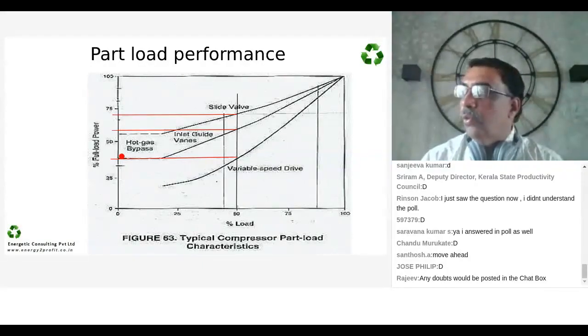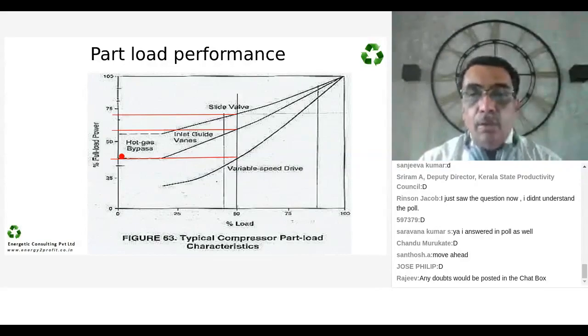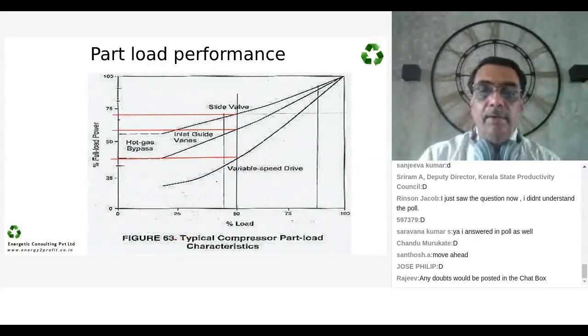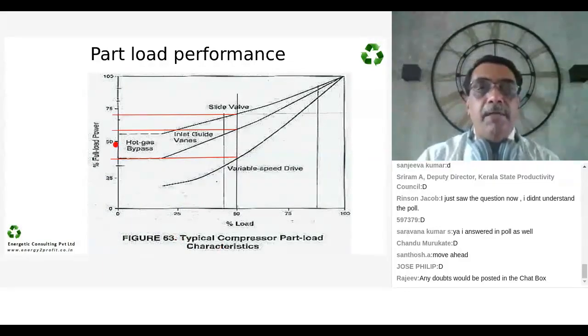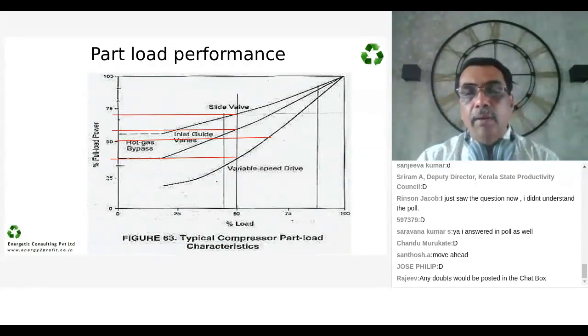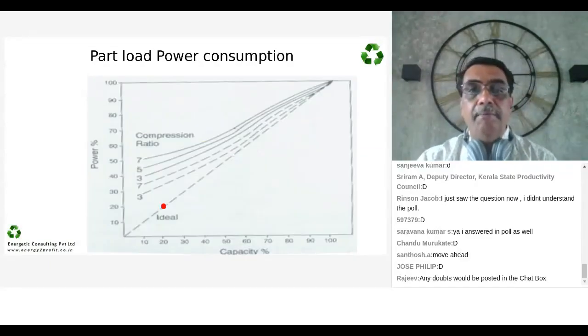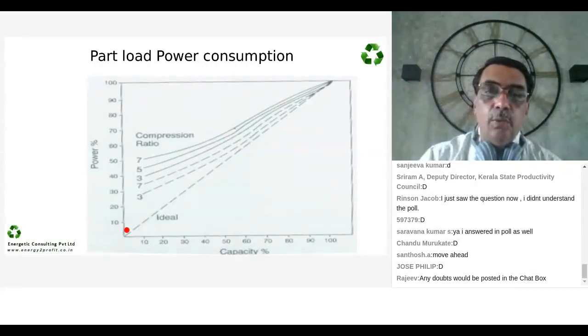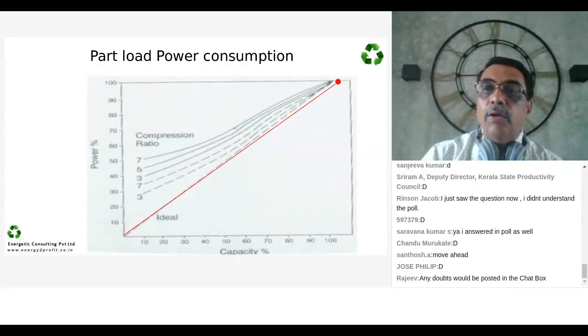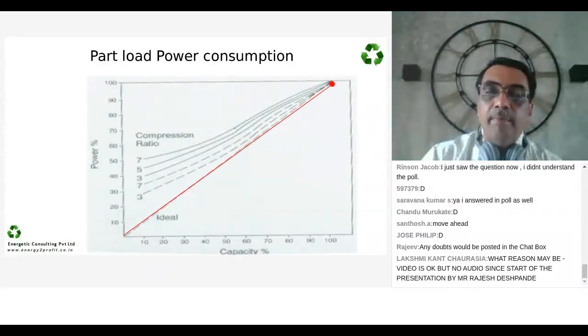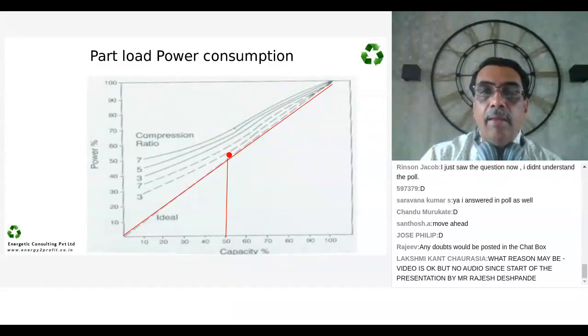Mind you, these are not universal fundamentals. If you have a screw compressor at 50%, you may operate at a similar load. Now, how do I know this? I go to the next chart. These are my compression ratio. Now, what is this ideal line mean? This ideal line means that if I have got 50% load, I would have 50% energy consumption, angle of 45 degrees.